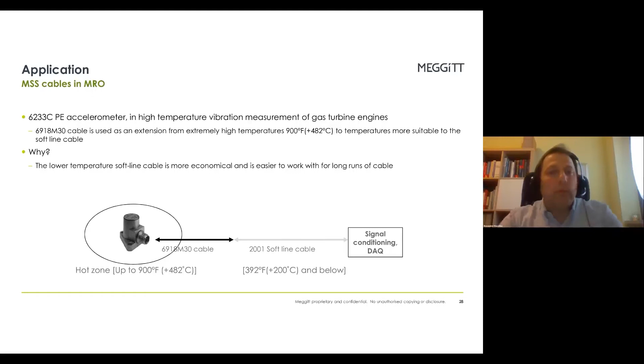A short length of 6918 M30 cable just out of the hot area, and then we use the 2001 soft line cable to the signal conditioning or data acquisition system. The reason to use the 2001 is just for economy, since it's not useful to have a very resistant cable where there's no need for temperature resistance.